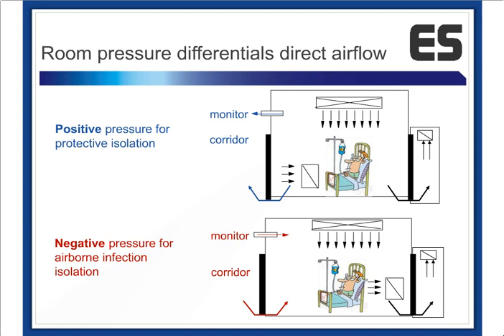And as you can see, in every space within the hospital, we will deliver air to that room, and we will be removing air from the room. In rooms where we need protective isolation, we'll be putting more air into the room than we're removing. That excess air will push itself out through the doors to the adjacent toilet room or to the corridors. And that helps ensure that contaminants are not going to enter those rooms. Another thing we would want to see in a protective environment room is HEPA filtration, which is a requirement of the guidelines and is 99.97% efficient, highly filtered air. So all of that supply air that's delivered to the room would be highly filtered.